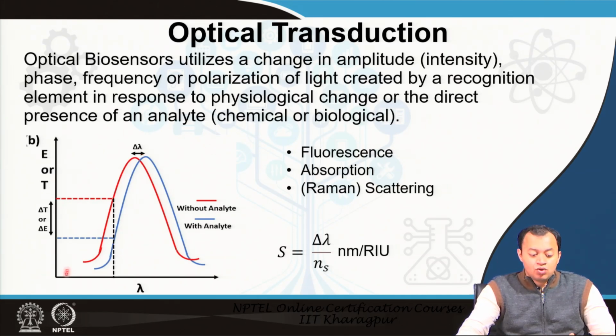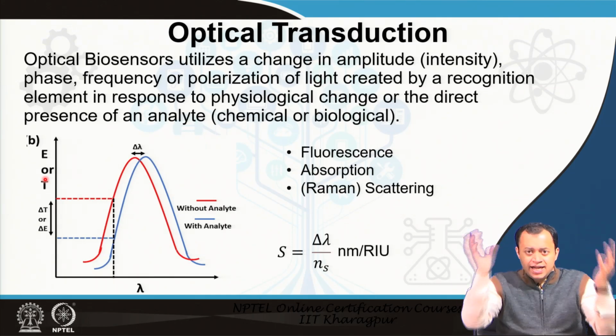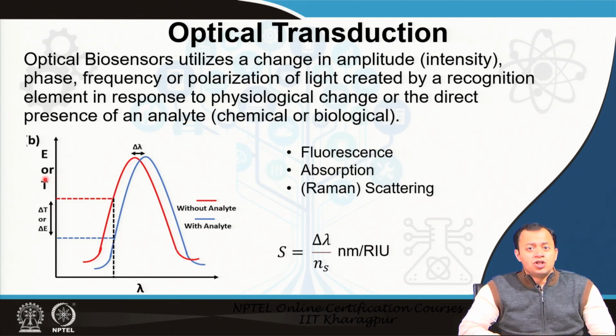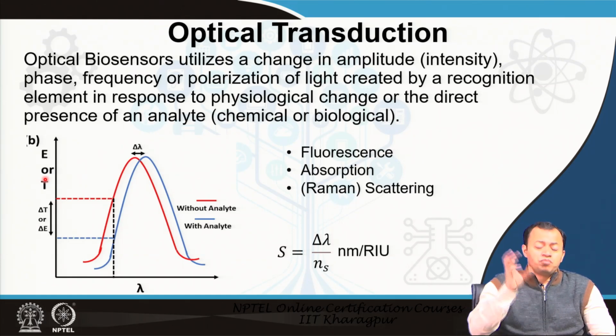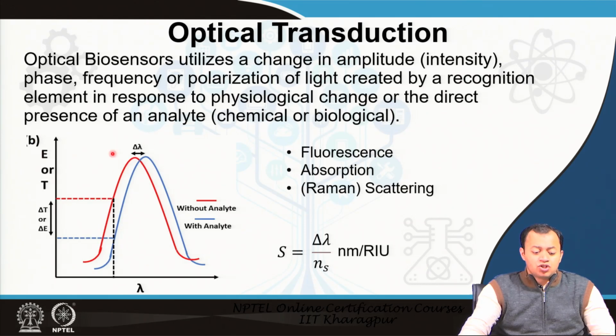Absorption: delta T or delta E, where E is for extinction coefficient and T is for transmission. Say the transducer at that particular frequency does not absorb anything, but when you have put a molecule, an analyte which absorbs, the overall response reduces because there is an absorption happening now in the entire system. And you remember my bioimaging part where I discussed that a particular material absorbs a particular frequency only. You put that frequency, you put that material on top of that and you see a particular bunch of frequency missing. IR absorption usually happens in infrared. Most organic compounds absorb something in the mid-infrared region, and you see a change in absorption.